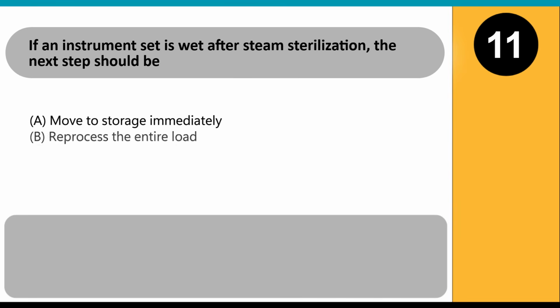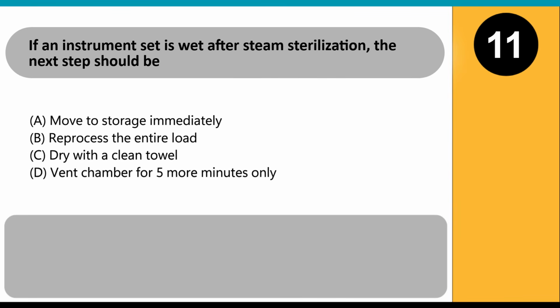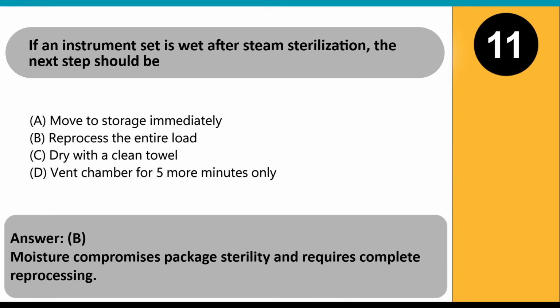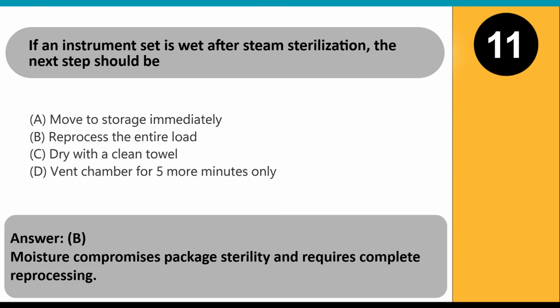If an instrument set is wet after steam sterilization, the next step should be A. Move to storage immediately. B. Reprocess the entire load. C. Dry with a clean towel. D. Vent chamber for 5 more minutes only. Answer B. Moisture compromises package sterility and requires complete reprocessing.